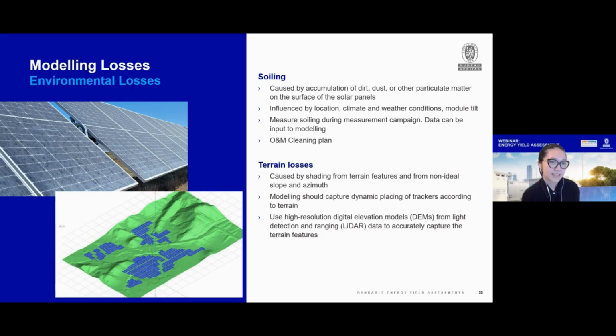The second environmental loss I'm classifying is terrain losses, caused by shading from the terrain, both outside of the array, like undulating terrain causing shading directly on the array, but also from the terrain under your array that forms a non-ideal slope and azimuth for your trackers or fixed tilt structures. Modeling should capture dynamic placing of these trackers according to terrain.